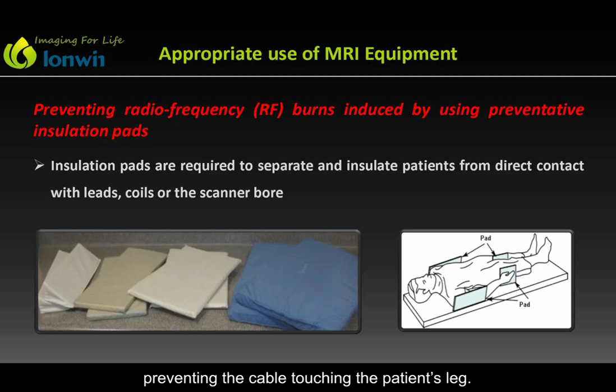Here is a real-life example of the correct placement of leads exiting the scanner for a patient in MRI. Note the pads placed between the patient's arms, preventing the patient's skin directly contacting the walls of the scanner bore, and the large insulation pad preventing the cable touching the patient's leg. The final step to promote MRI safety that we will discuss is to ensure that you have established protocols for MRI emergencies.